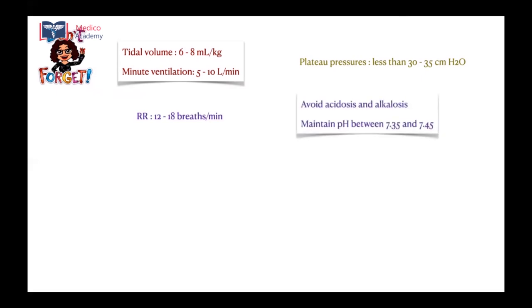Minute ventilation of 5 to 10 liters per minute is sufficient. Plateau pressures should not go beyond 30 to 35 centimeters of water. Respiratory rate to begin with can be 12 to 18 breaths per minute, so that you avoid acidosis and alkalosis, and maintain a pH between 7.35 and 7.45. The inspiratory time should be between 1 and 1.5 seconds. And the IE ratio should be maintained between 1:2 and 1:3.